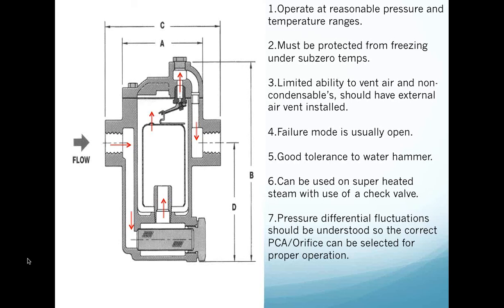Limited ability to vent air and non-condensables. On every steam system, I look for air vents and vacuum breakers, and to me they're very, very important for a couple different reasons.